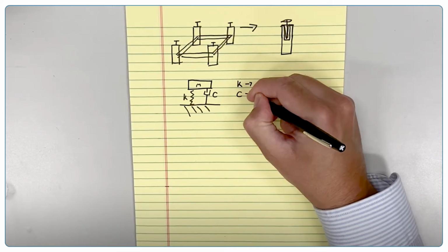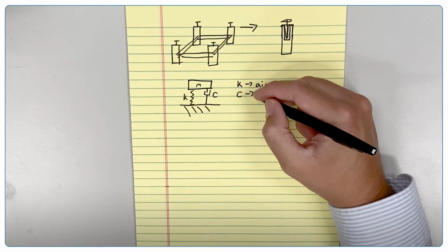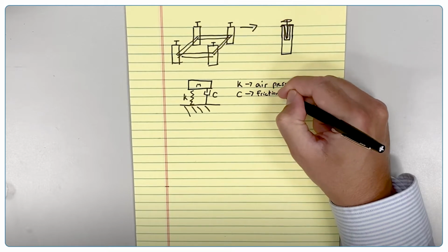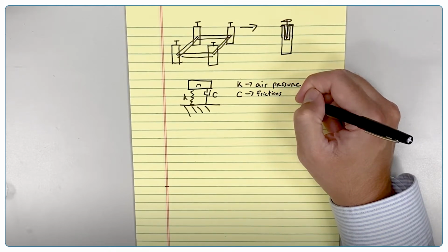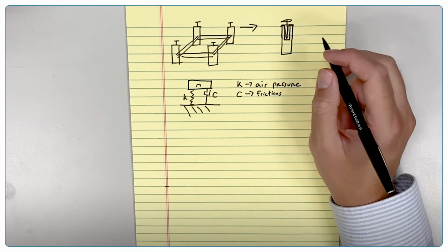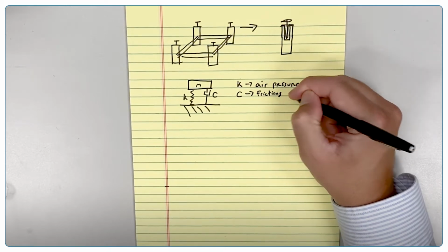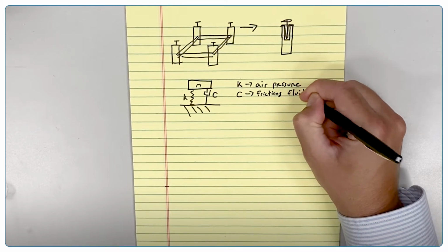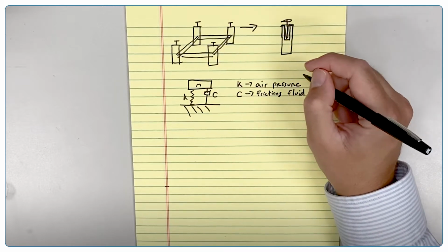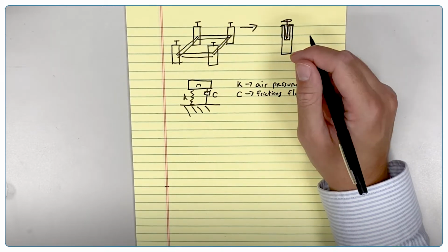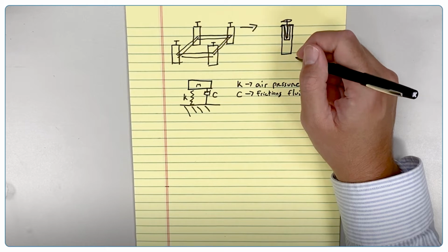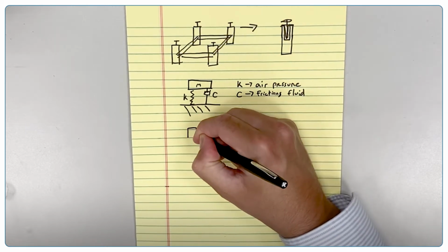And your damping coefficient C is typically provided by friction of mechanical components, such as resistance within the rubber diaphragm itself, which provides the air seal, but also can be increased by adding some sort of viscous fluid to provide additional damping. Pneumatic isolators like this are available off the shelf from TMC, and they can be easily incorporated into any square cross-section frame design.